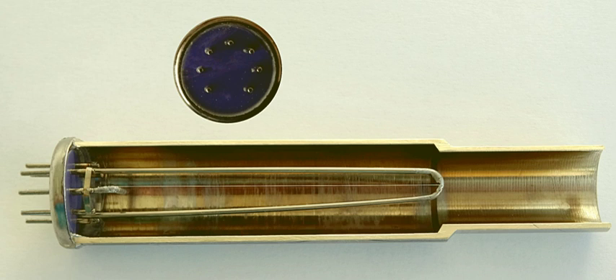The Pirani gauge is a robust thermal conductivity gauge used for the measurement of the pressures in vacuum systems. It was invented in 1906 by Marcello Pirani. Marcello Stefano Pirani was a German physicist working for Siemens and Halske, which was involved in the vacuum lamp industry.